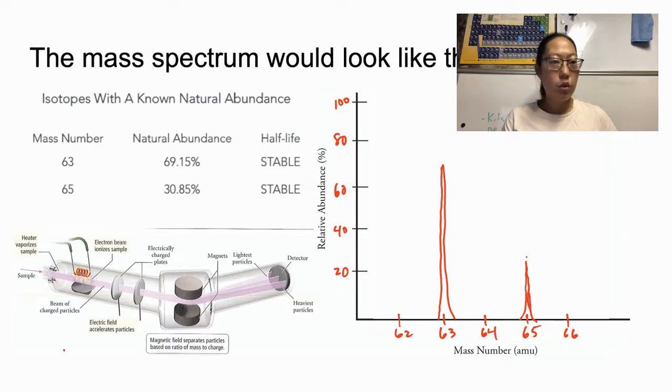But in general, when you ionize a sample of something, there is something called the ionization cross-section. It's kind of a probability of how highly ionized you can make a particle. And so the probability for ionizing something once usually is much greater than ionizing it twice. So most of the particles will go through and get ionized the same way. There will be some that will not because there is some probability of them getting ionized twice or 3 times or 4 times, and so forth. And so those will cause peaks in your mass spectrum.